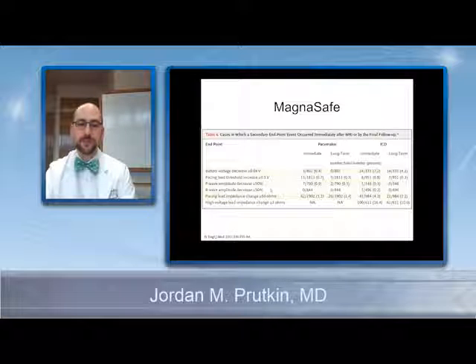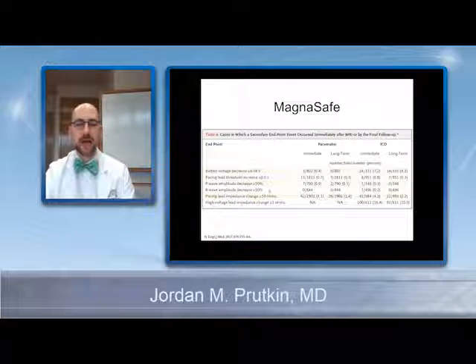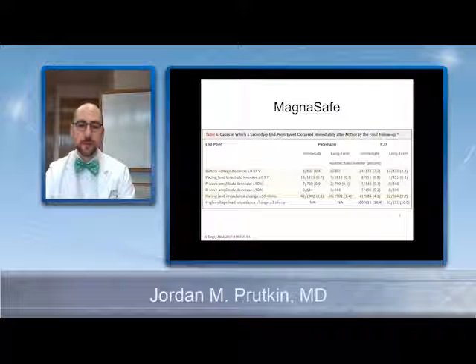Some changes in the P waves and R waves, and this has to do with sensing how well the device sees the intrinsic cardiac signal. For R waves, there was none of them that had any significant long-term changes, and very rare was the P wave, which is the atrial lead, having any significant change. And then impedances, and this ties into the longevity of the system, and for high voltage impedance, it may get into issues of how well an ICD can shock someone. And there were some changes in this, but I would argue these probably aren't very significant changes in the end.